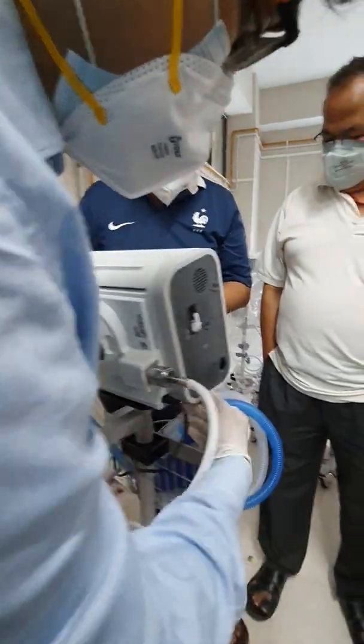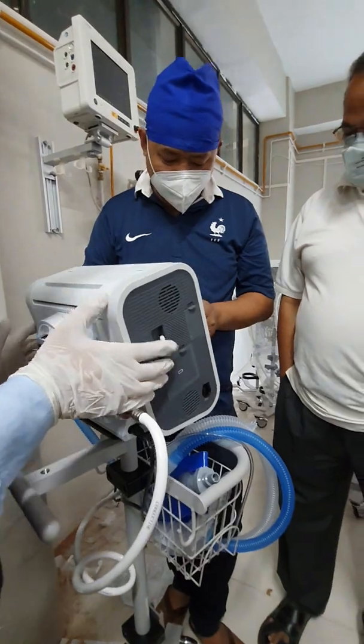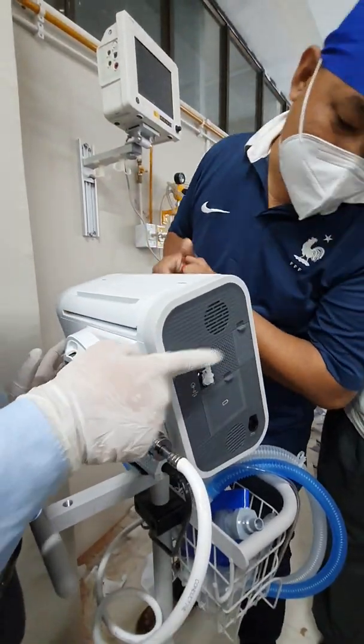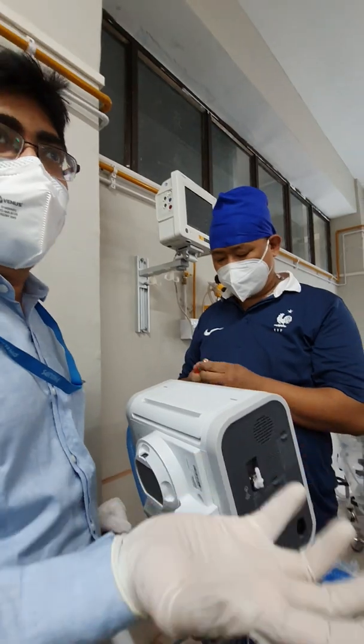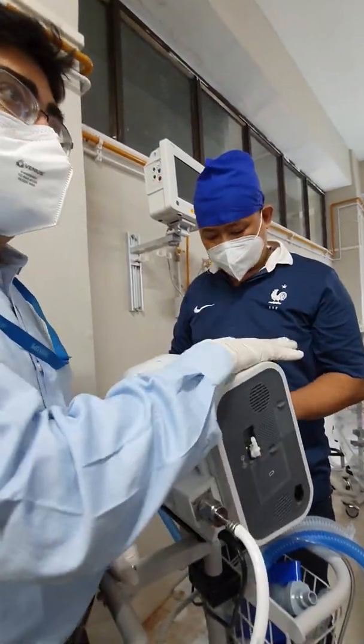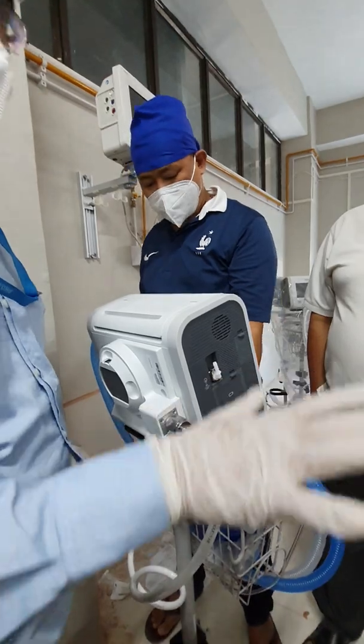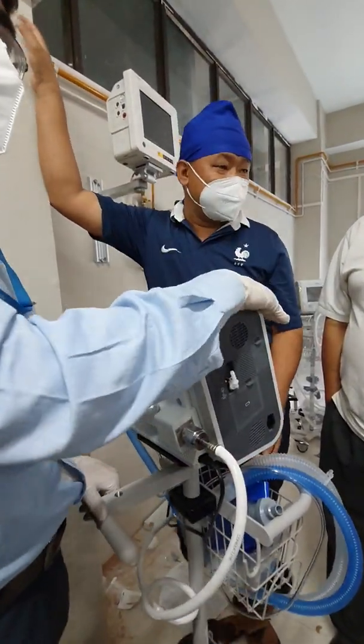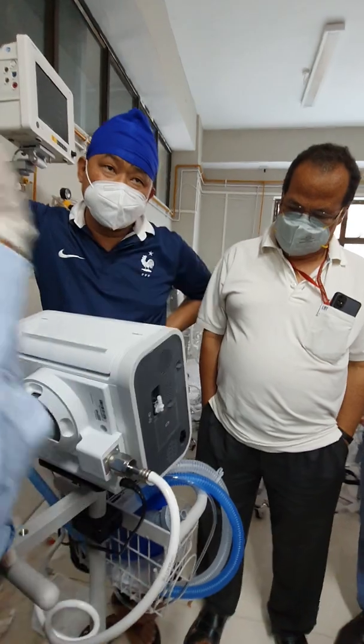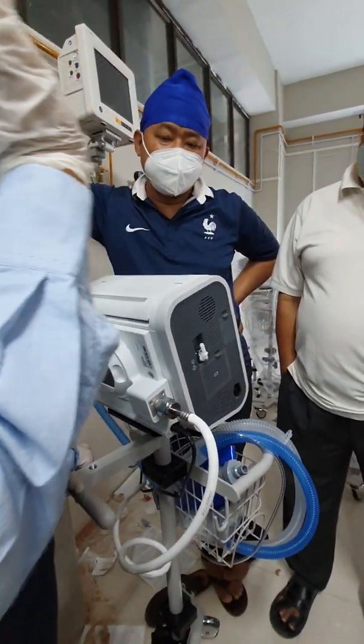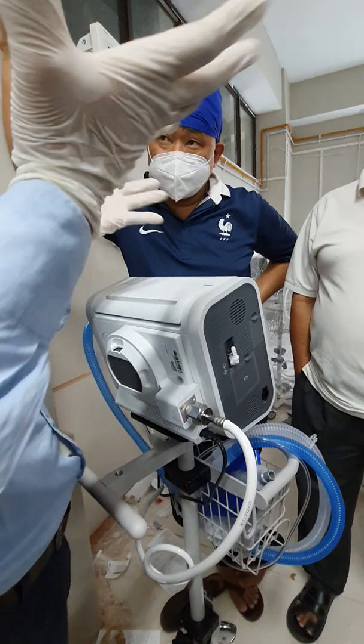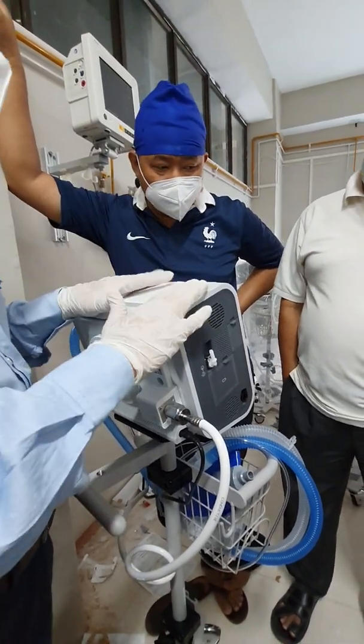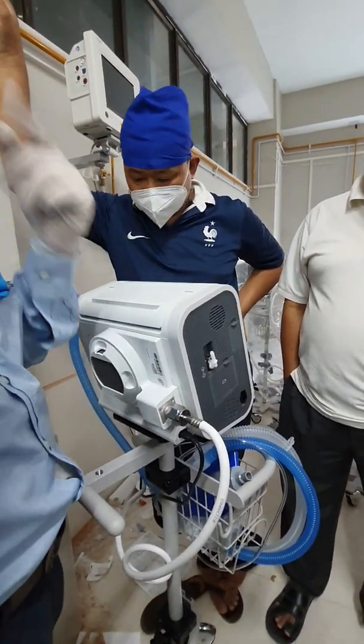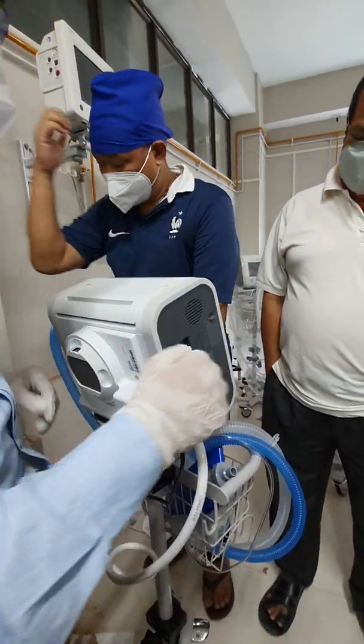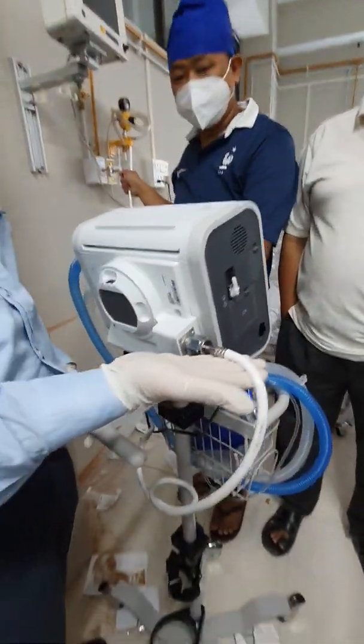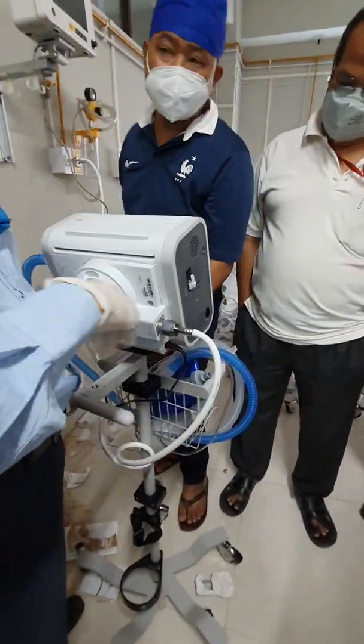Okay, so this is the low pressure oxygen inlet. You can connect it with a flow meter, like a 15 liter per minute flow meter, and you can deliver both NIV and invasive ventilation. For invasive, you can go up to a maximum of 85% FiO2. With NIV, since leakage is obvious, you can go up to 65% FiO2 with good leakage proofing. This is the high pressure inlet. Here you don't have any limitation: from 21 to 100%, anything you can.